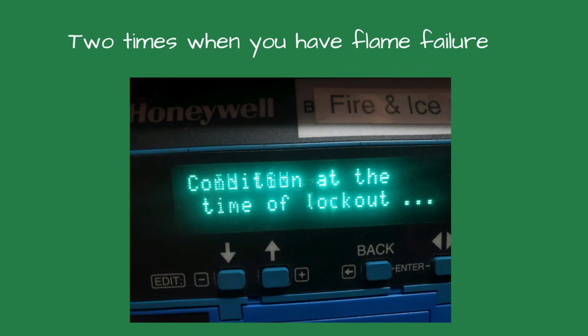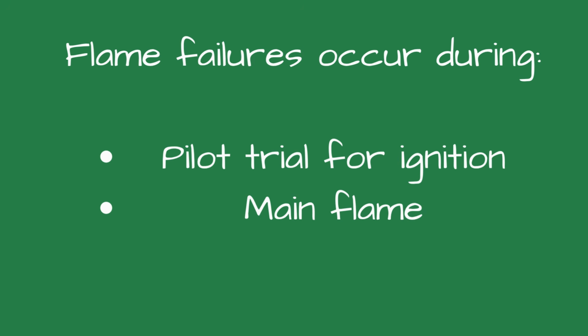When does a flame failure occur? Flame failures typically happen in either one of two stages. Number one, during the pilot trial for ignition, PTFI. It's the most common time for a boiler flame failure. Number two is during main flame operation. Again, it's less common. Knowing which stage the failure occurs narrows your search dramatically.